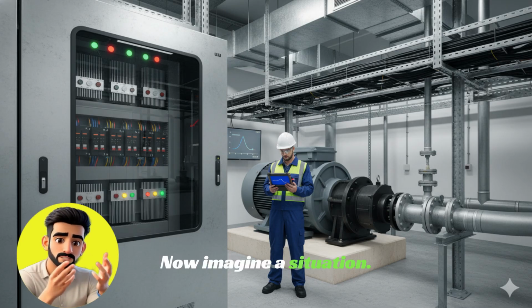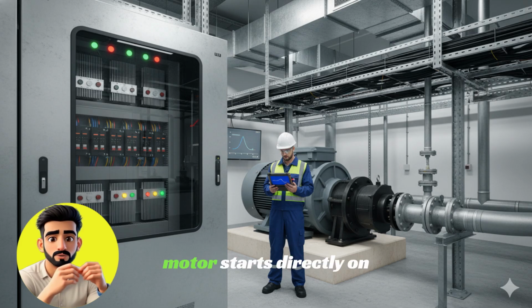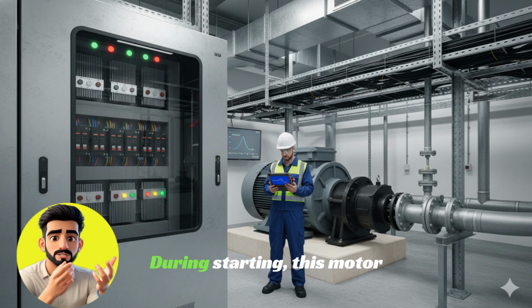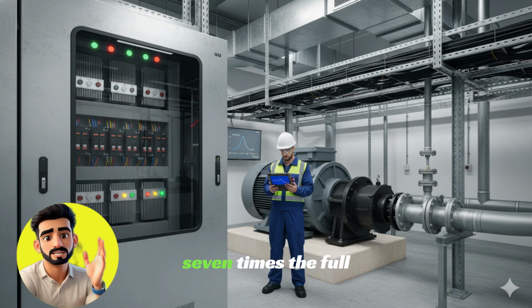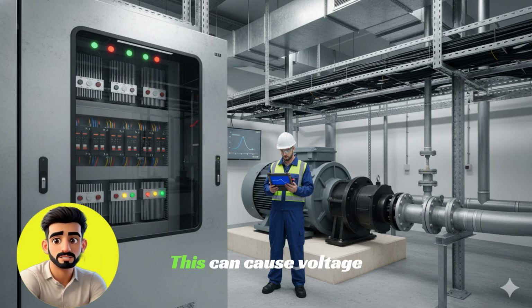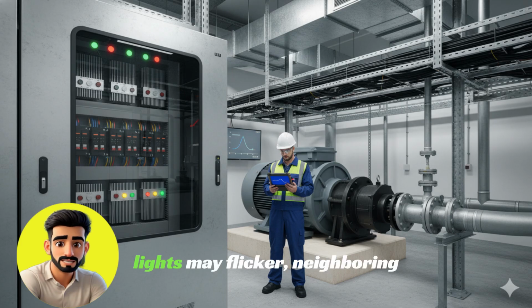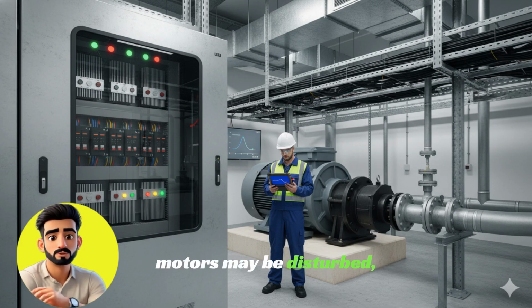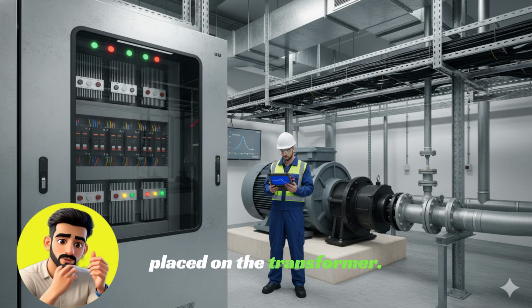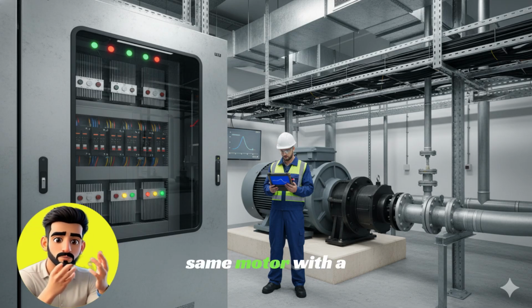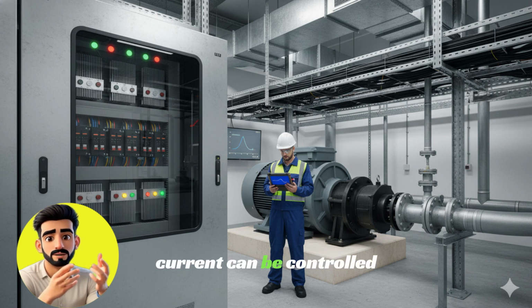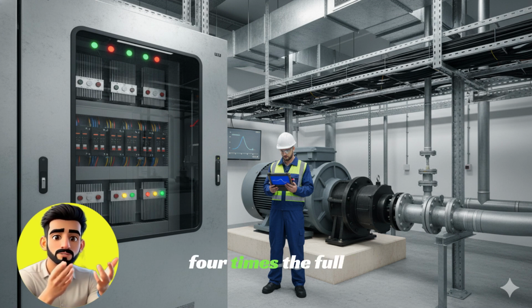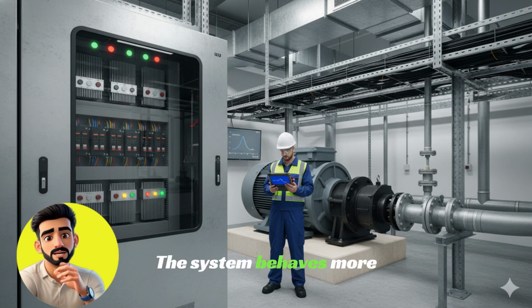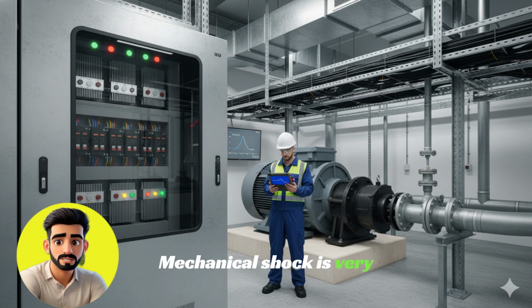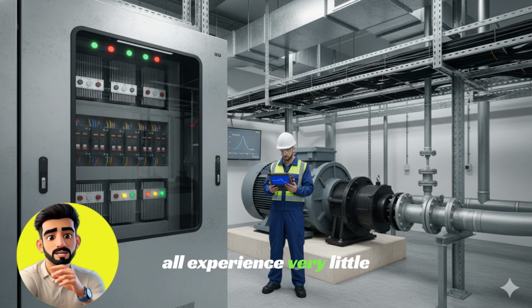Now, imagine a situation. A 400 kilowatt motor starts directly online. During starting, this motor can draw 6 to 7 times the full load current. This can cause voltage dips in the system. Lights may flicker, neighboring motors may be disturbed, and unnecessary stress is placed on the transformer. If we start the same motor with a soft starter, the starting current can be controlled to around 3 to 4 times the full load current. The system behaves more smoothly. Mechanical shock is very minimal. Pipelines, couplings, shafts all experience very little impact.